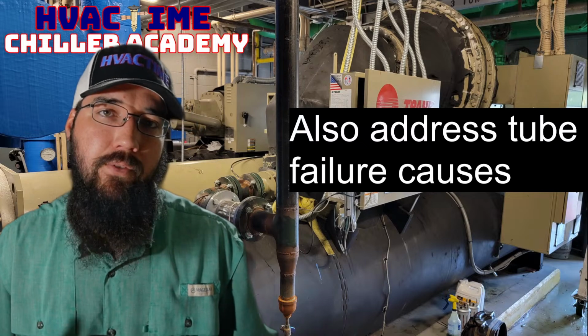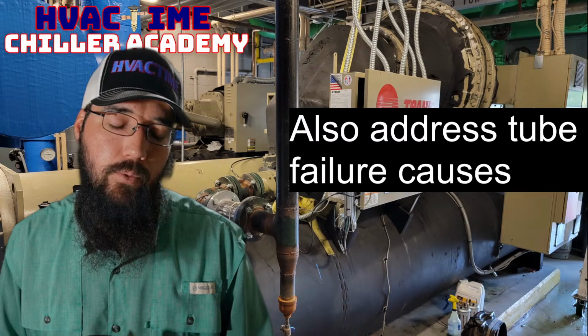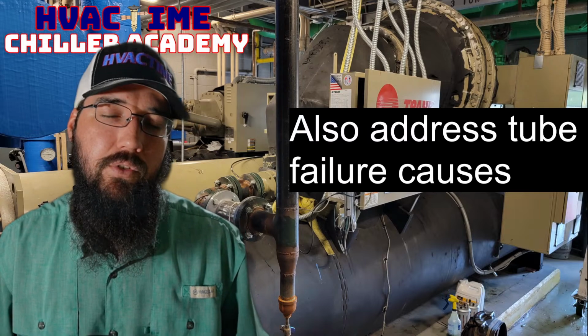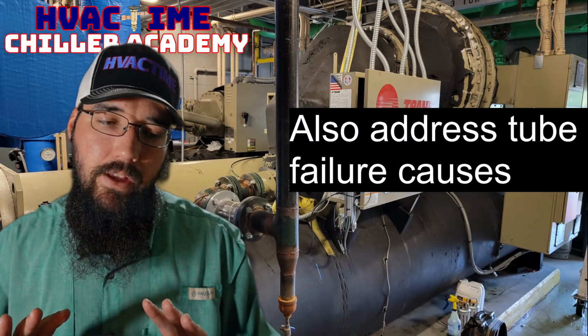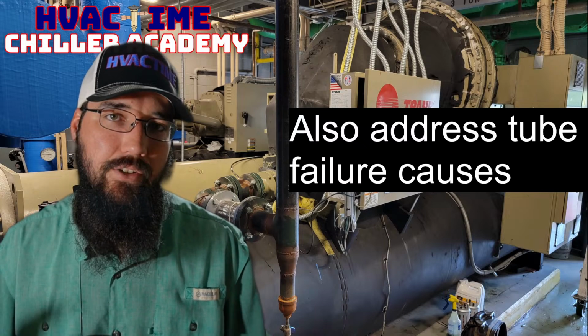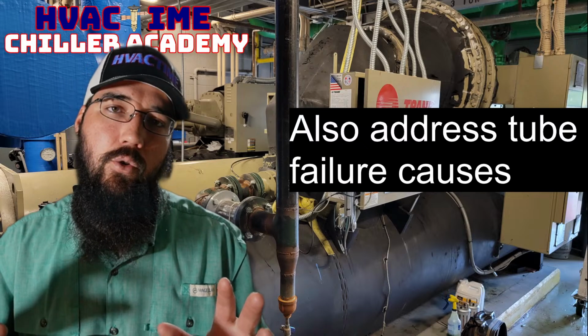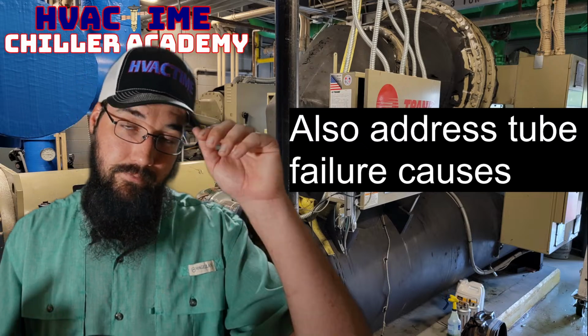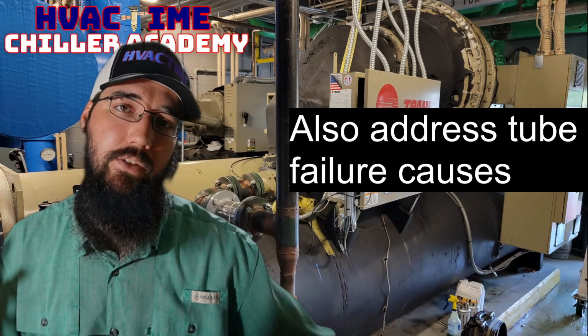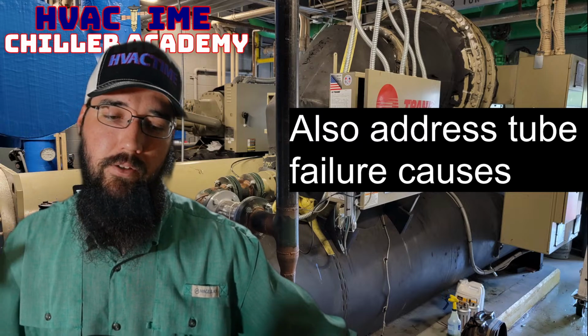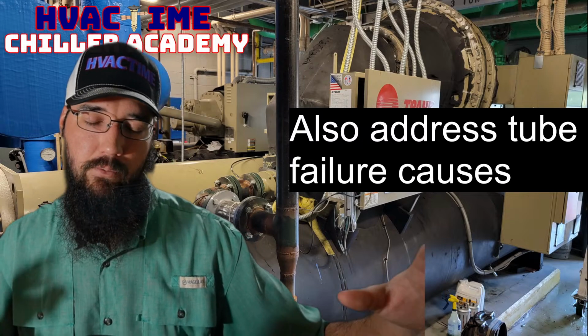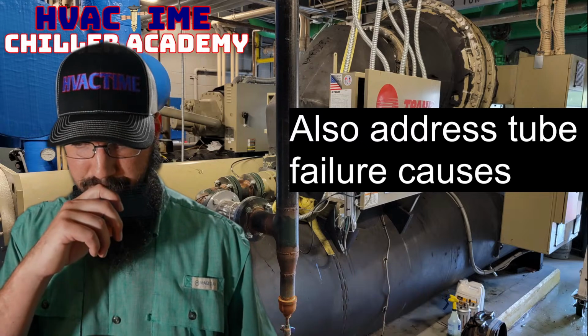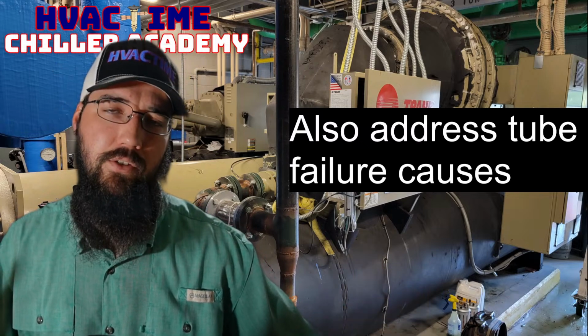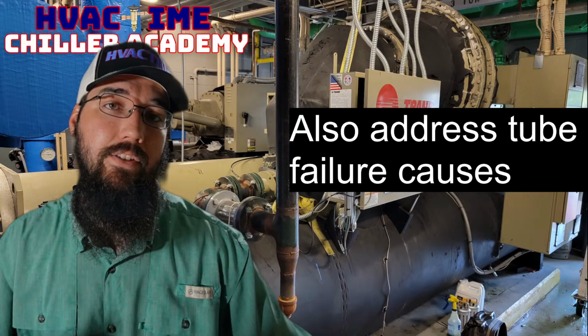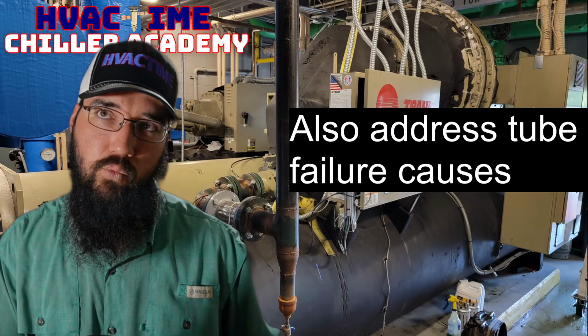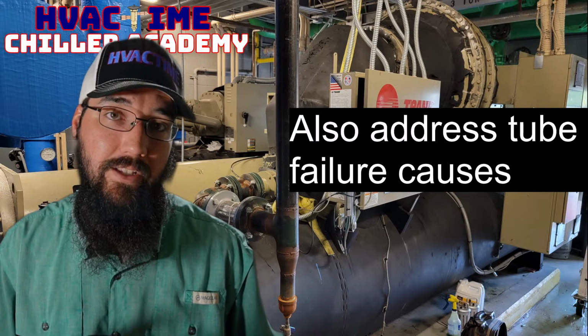And depending on the type of failure, depends on what we can do. The most common thing to do is, ideally, you catch it early enough where it's not a catastrophic failure. In that event, you're going to plug that tube with a set of plugs. Now, to do that, you're opening up both sides of the tube sheet. That'll depend on your piping, on how difficult that will be, whether it's a 2-pass or a single pass or otherwise. But you're going to open up both ends of the tube sheet, and then that particular tube that is leaking, or let's say you had an eddy current test done and you found that you had a couple of tubes in there with a really thin wall, so they were dangerously thin.